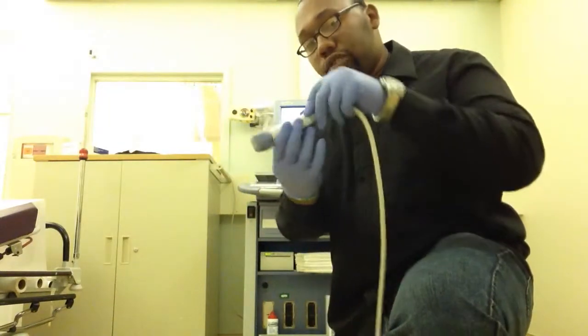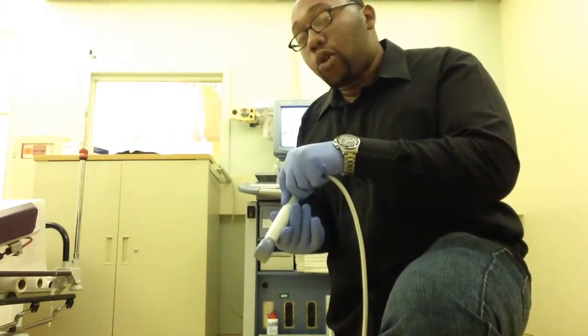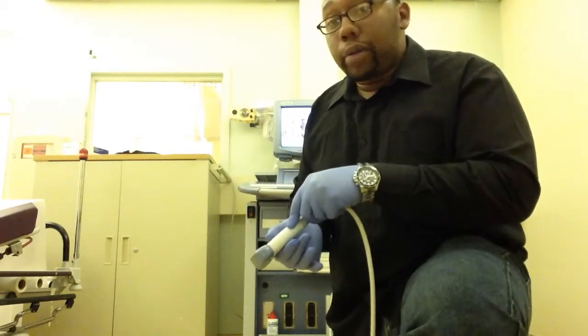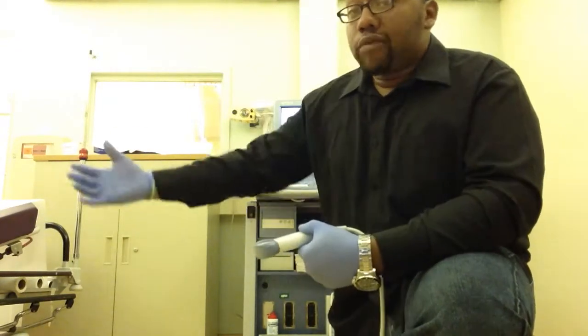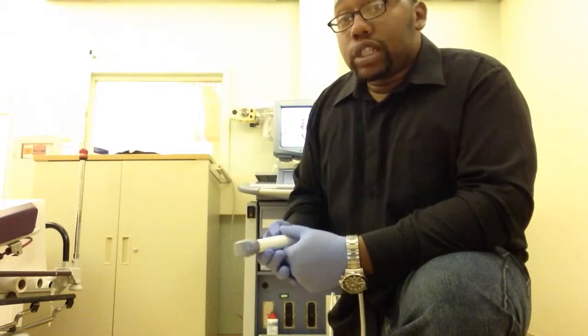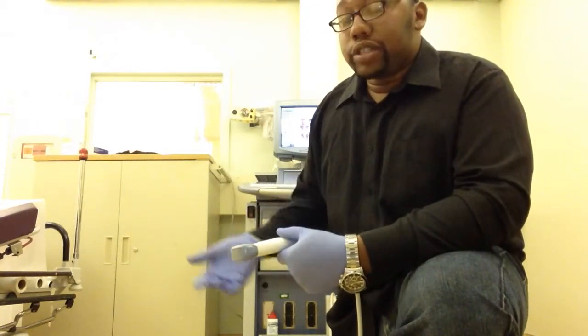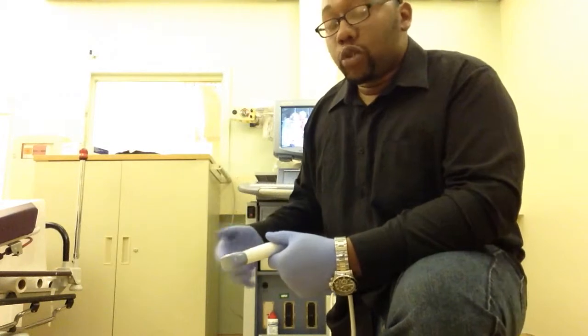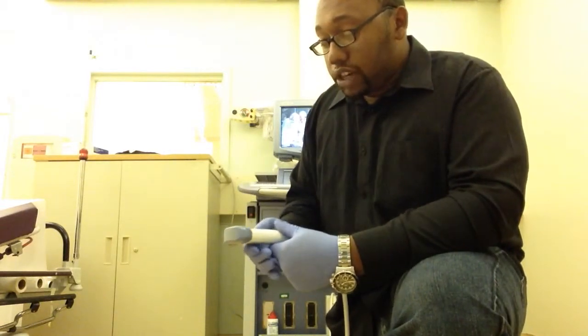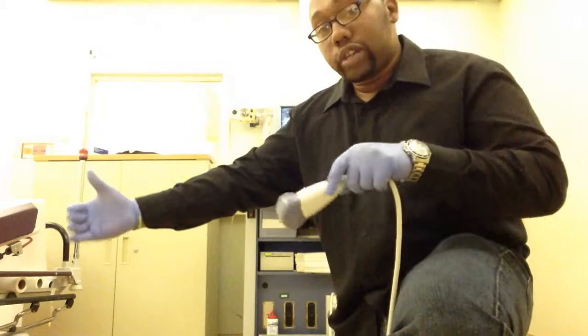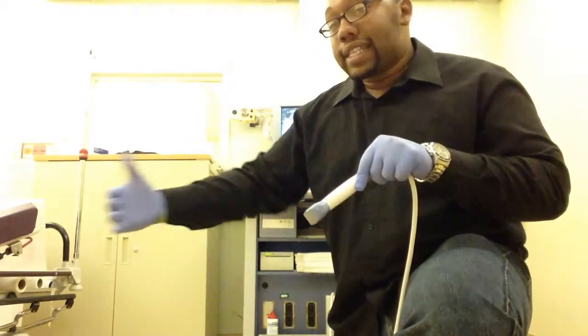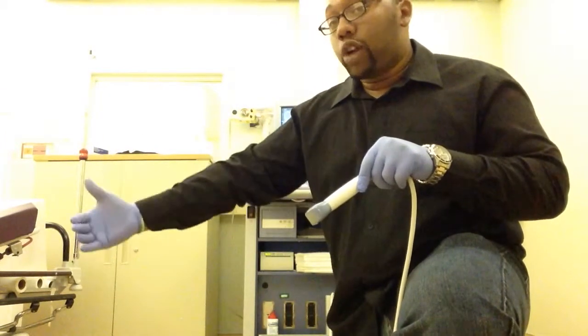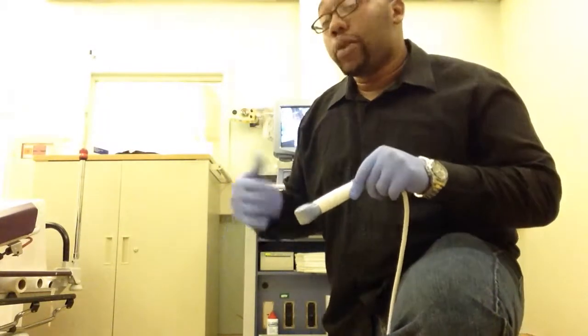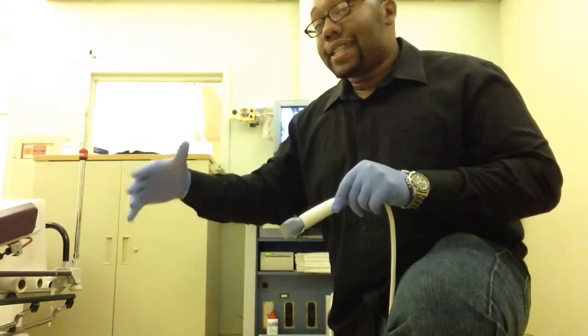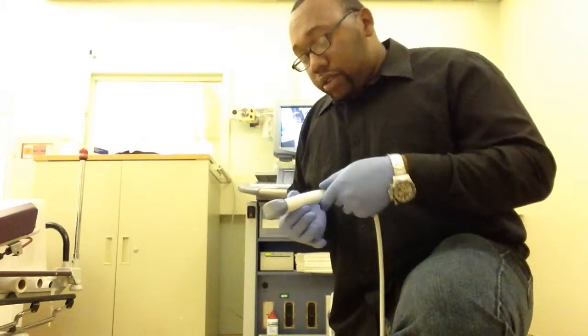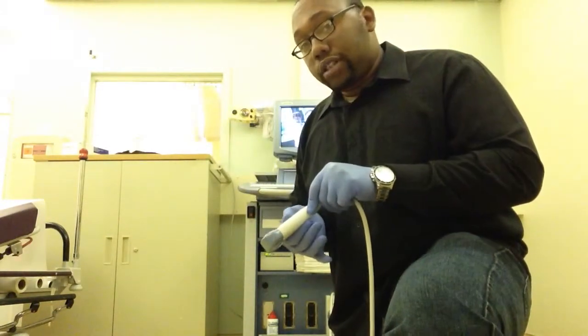We're going to have this transducer in a fixed position down in that water bath. Across from it, approximately 250 millimeters away, we're going to have what's called a hydrophone. A hydrophone is a device that captures sound and converts it back into voltage so we can get a reading. Any sound that passes the hydrophone, we don't want to reverberate off the walls of the water bath and come back across the hydrophone, because then we'll get an improper reading. So we want any sound that passes it to be absorbed. Okay, so we're going to set that transducer down into the water.